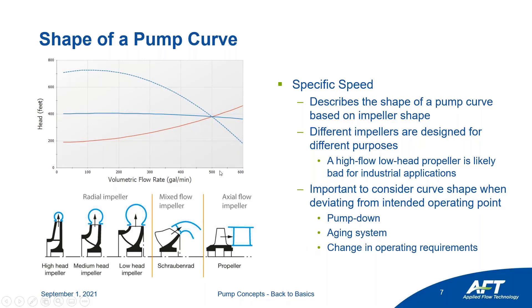Final considerations: a change in operating requirements — needing to increase or throttle flow down to 400 GPM — means the amount of pressure you need to remove will be vastly different depending on the pump curve. All of these considerations can be made in Fathom by specifying the curve, making tweaks to the system, and seeing the resulting head instead of doing slow hand calculations.